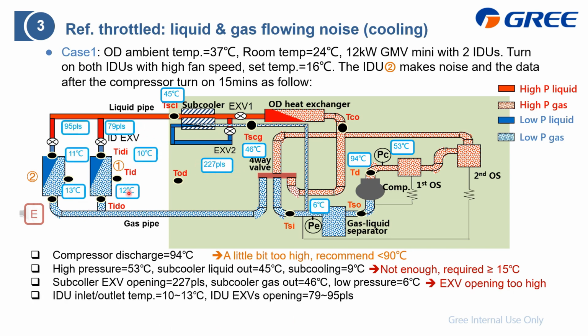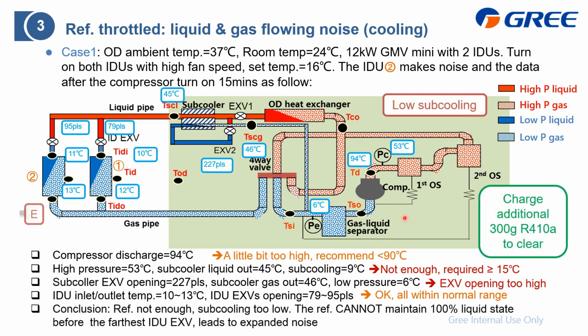So how about the indoor unit pressure and the temperature and the EXV opening? It's just like this. From this data, we find that it is still okay, all within the desired range. And as the noise is still continuous, our conclusion is the refrigerant is not enough, maybe leakage, or at the installation stage it was not charged enough, and the refrigerant cannot maintain the liquid state when we get to the furthest indoor unit, which is here, and this also leads to the noise. After we reached this conclusion, we had the serviceman charge an additional 300 grams, and this problem cleared.